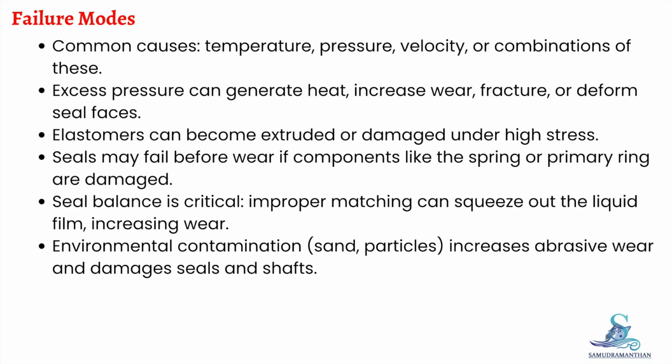Seal faces may fail before natural wear if the spring or primary ring is damaged. Improper seal balance can squeeze out the lubricating liquid film, increasing wear. Environmental contaminants like sand can embed in elastomer seals, causing abrasive damage to the seals and shafts.